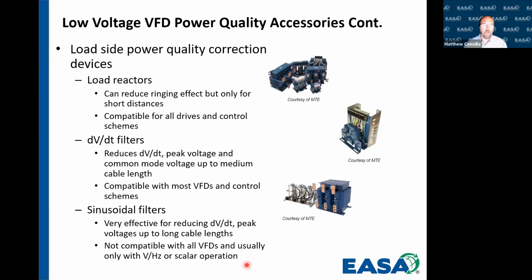So what can we do on the load side to help prevent things? Well, we can use load reactors, and they can reduce the ringing some, but really only for a short distance. A lot of drives are compatible, and almost all control schemes can use load reactors. There's a lot of white papers out there that talk about the effectiveness of a load reactor, and as we've started to learn more, we want to look a lot more closely at what we call dV/dt filters as a minimum. These dV/dt filters actually reduce that rate of rise and the peak voltage, and some of them can even reduce common mode voltage, which is another way that we get bearing currents, up to a medium cable length. So, somewhere in the ballpark of 300 to 500 feet.